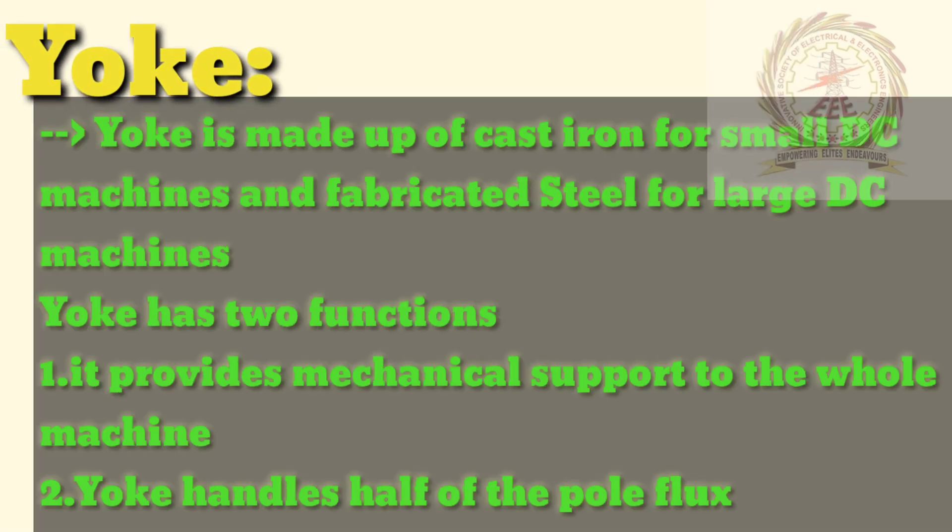Let's start from yoke. Yoke is made up of cast iron for small DC machines and fabricated steel for large DC machines. Yoke has two functions. First one, it provides mechanical support to the whole machine. Second one, yoke carries half of the pole flux.